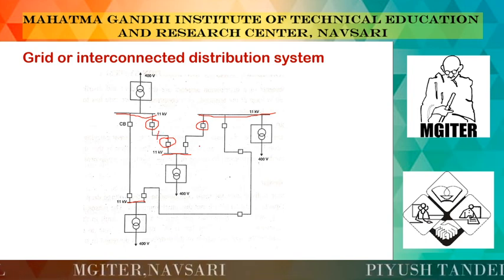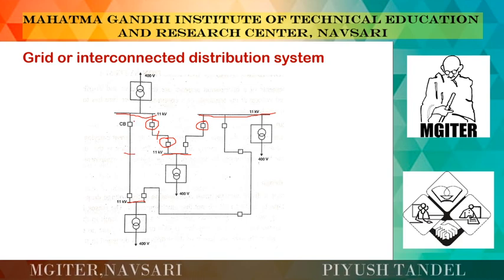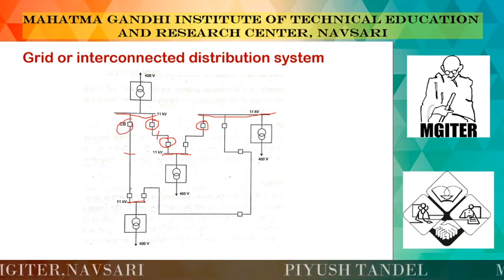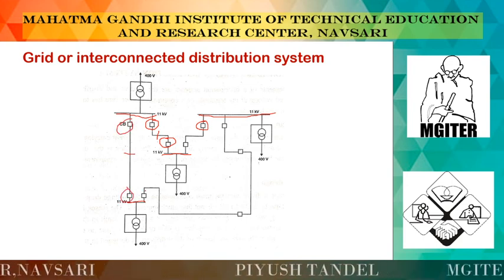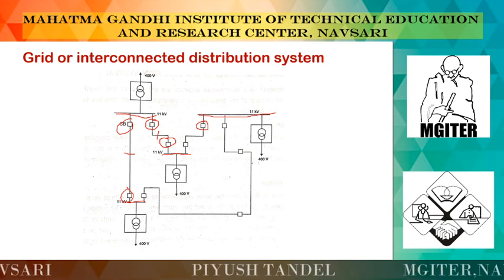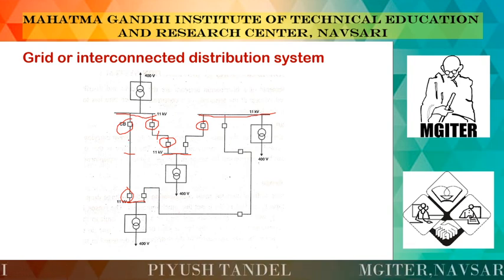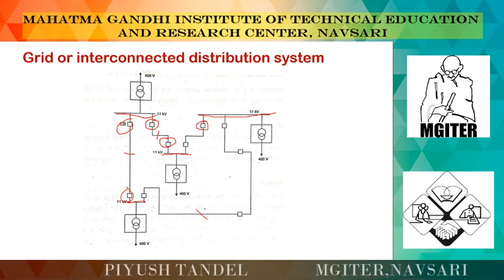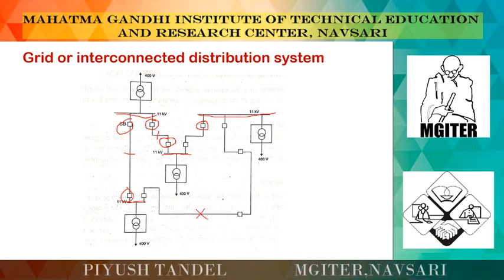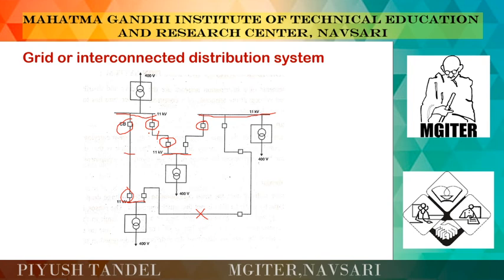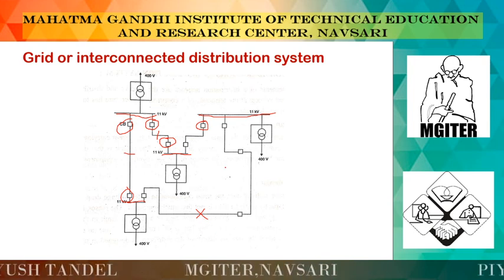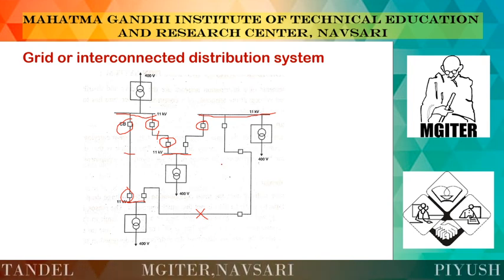So whenever a fault occurs in between these cables, the circuit breaker isolates this portion, and the load is fed from the other part, from this path. If this part is the faulty part, then the current is fed from this part only. So the continuity of power increases greatly inside the grid, or interconnected, distribution system.